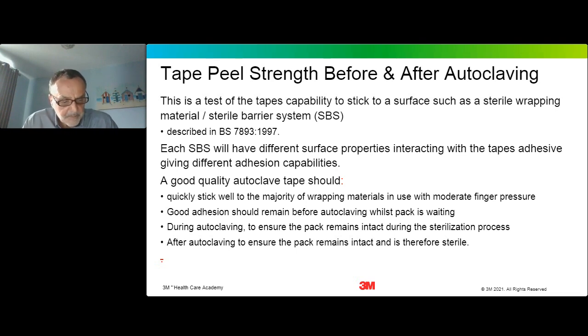As I stated earlier, each sterile barrier system has different surface properties, and the tape will interact with that surface differently. A good quality tape should stick well to the majority of wrapping materials used, after application by moderate finger pressure - you shouldn't need to put your whole body weight on the tape to get it to stick.